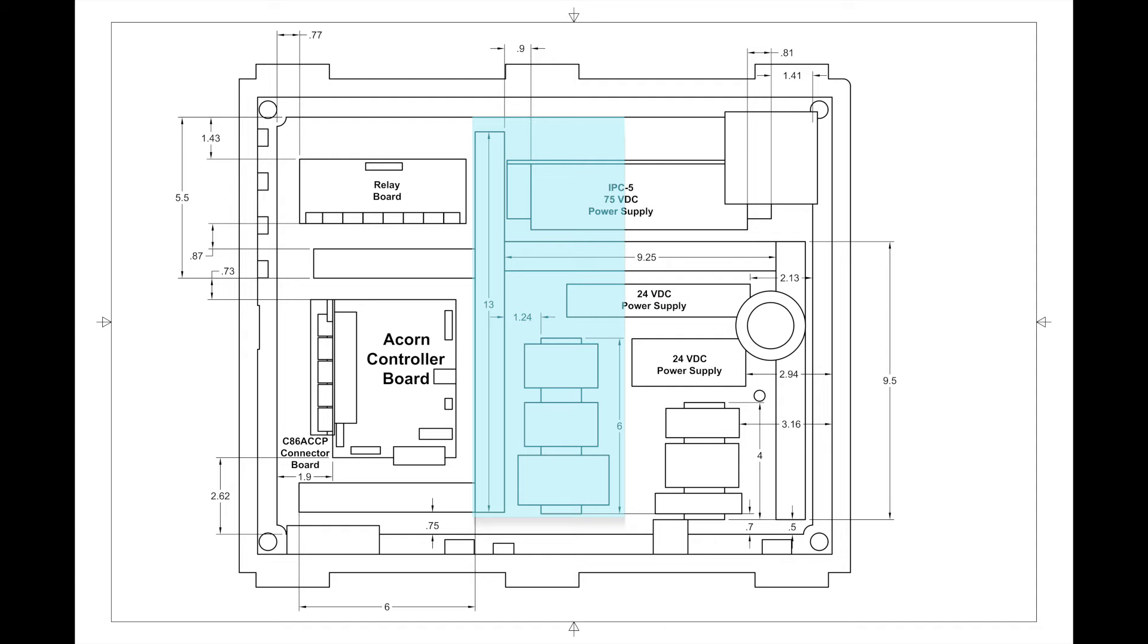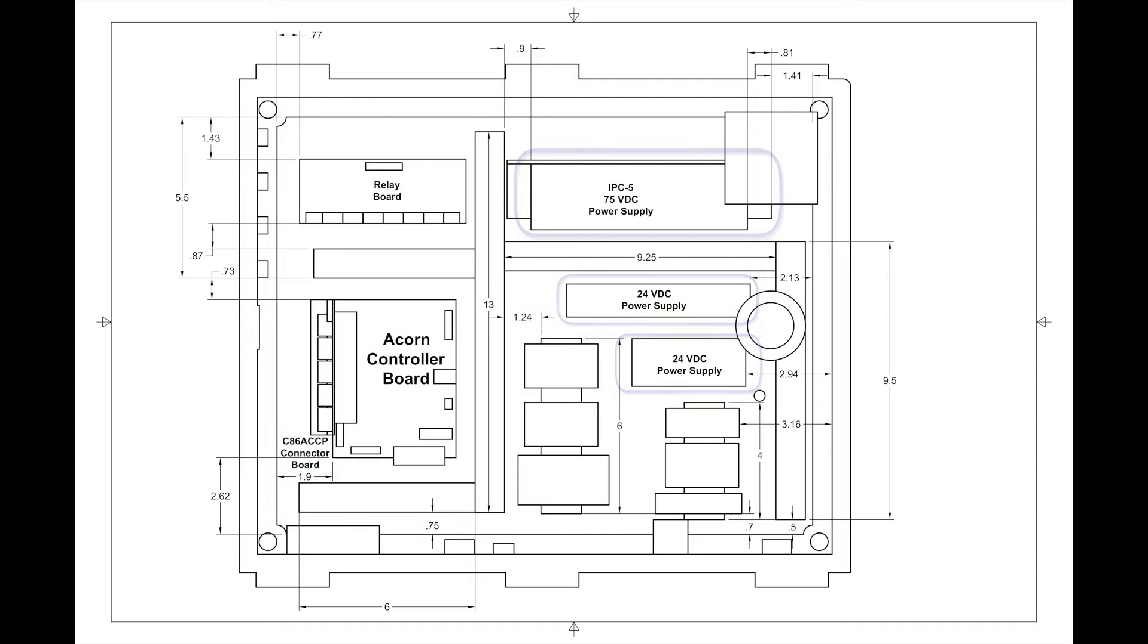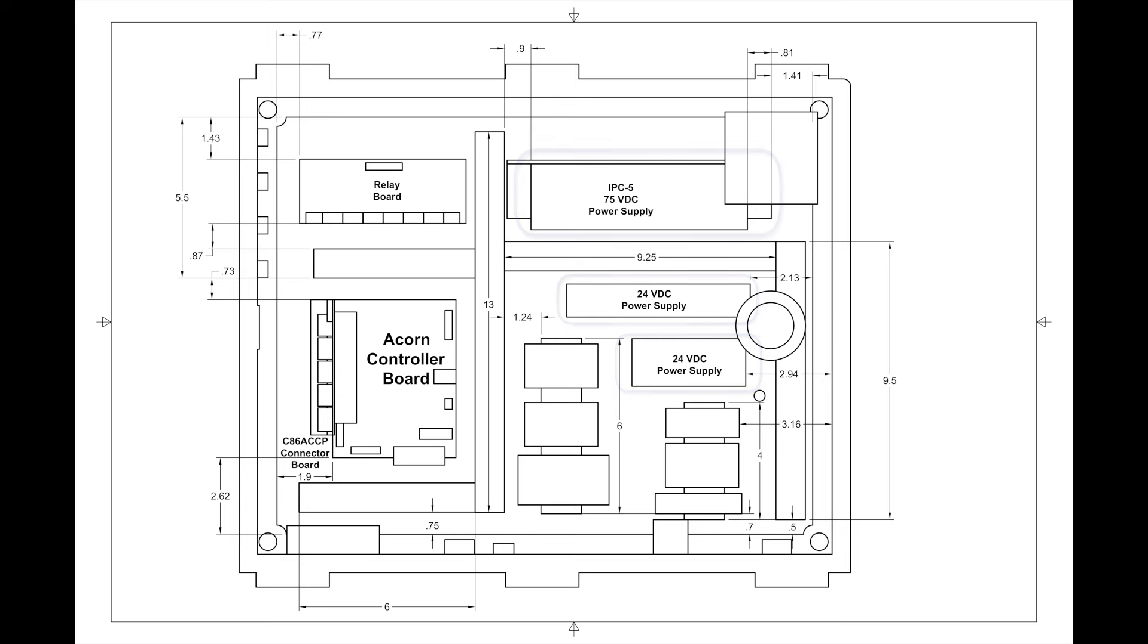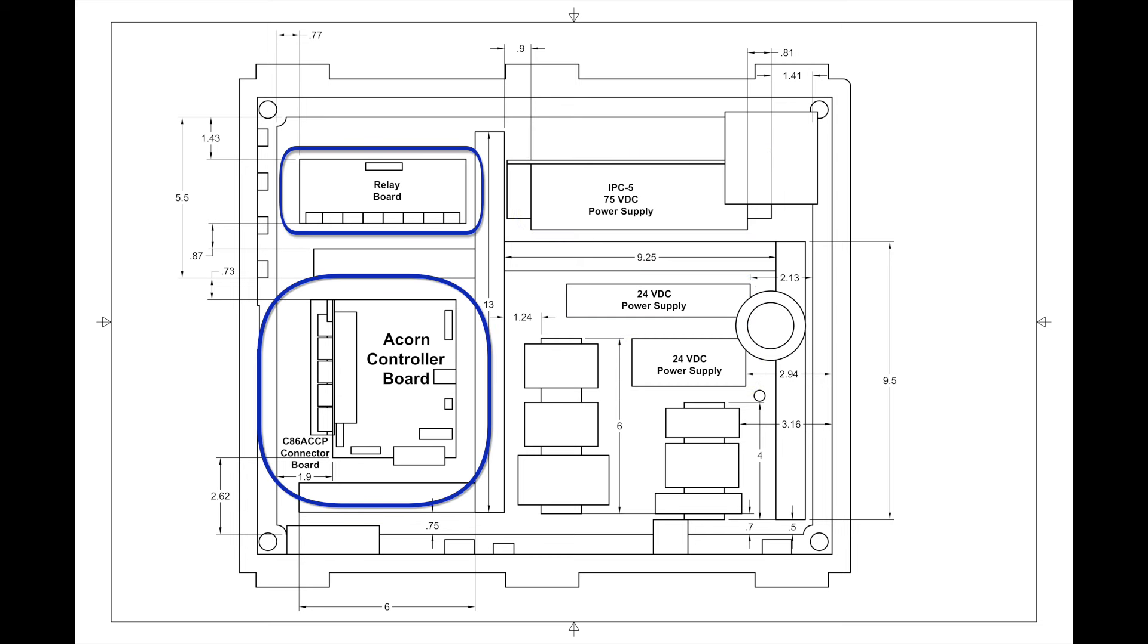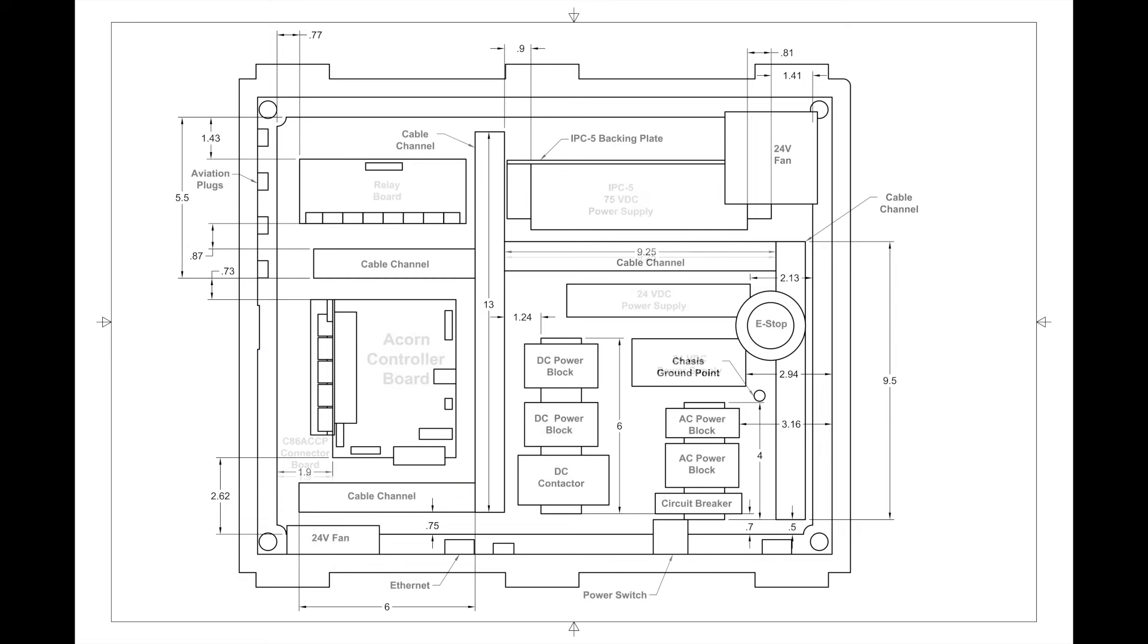The middle is for DC power and the left side is for controllers and logic. The power supplies are co-located and the ACORN, relay and connector boards are placed close to the perimeter of the enclosure to simplify cable access and to limit the interactions between logic and power cabling.